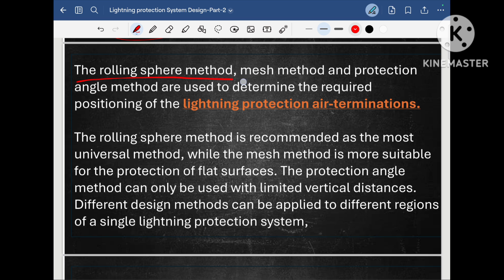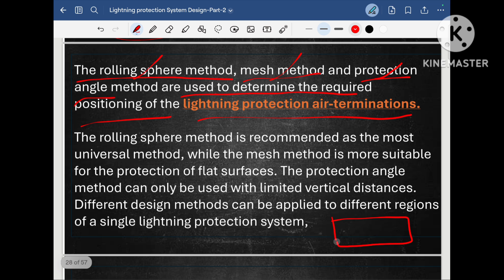The rolling sphere method, mesh method and the protection angle method are used to determine the required positioning of lightning protection air terminals. The motto of all these methods is to determine the location of air terminals. For example, I have a worker accommodation — any of these methods I will use to decide the lightning protection system. The location of the air terminal rod will be determined by whichever method is used for the designing of the lightning protection system.